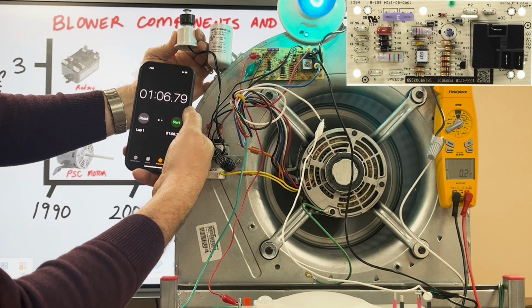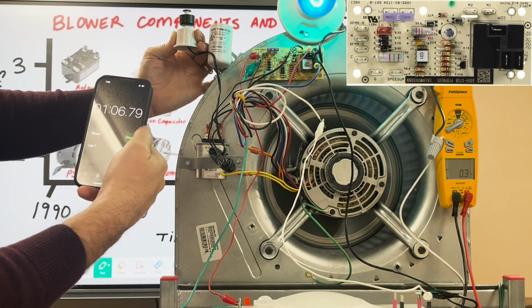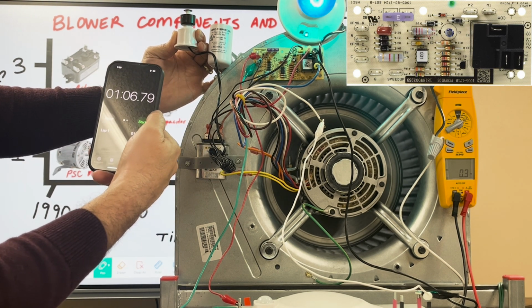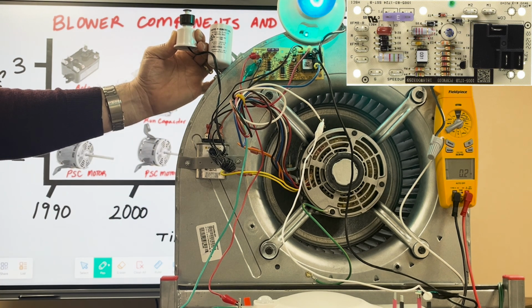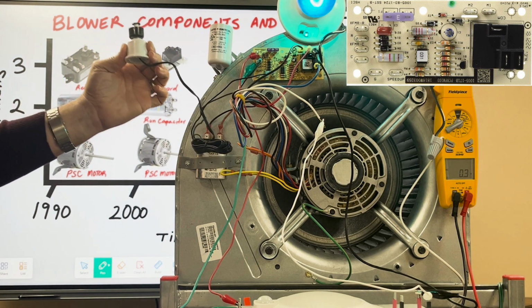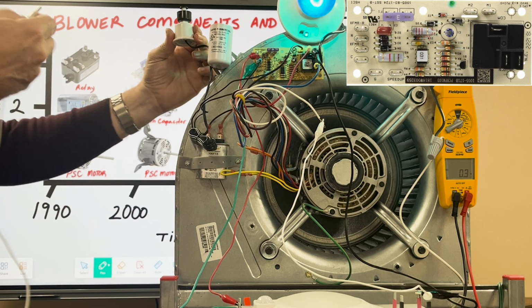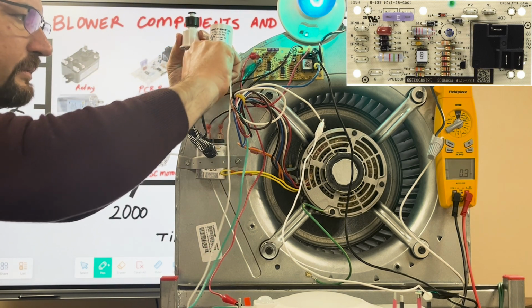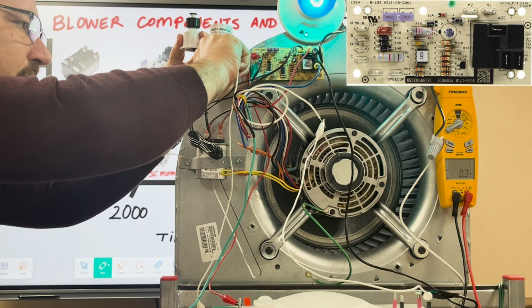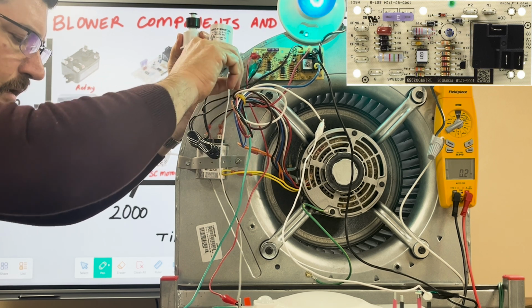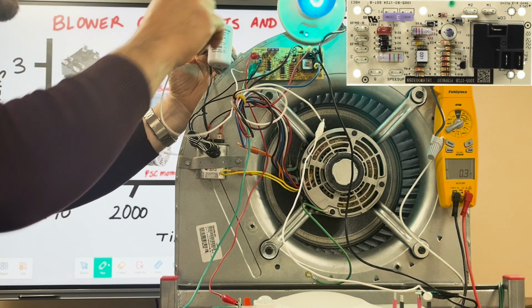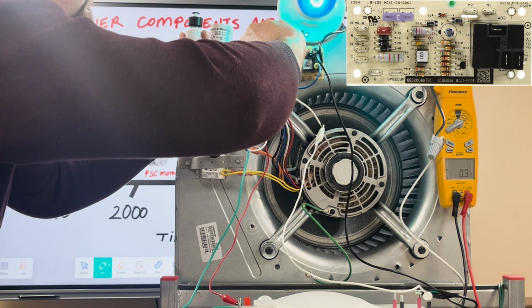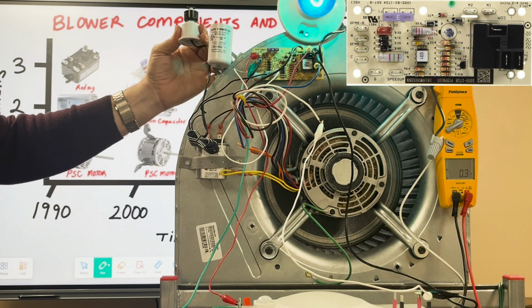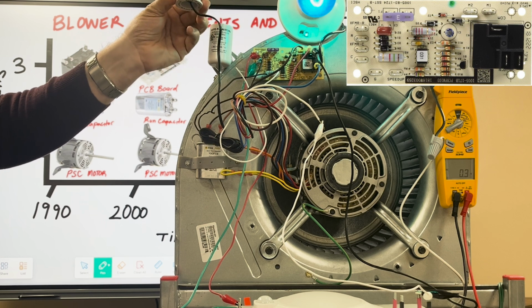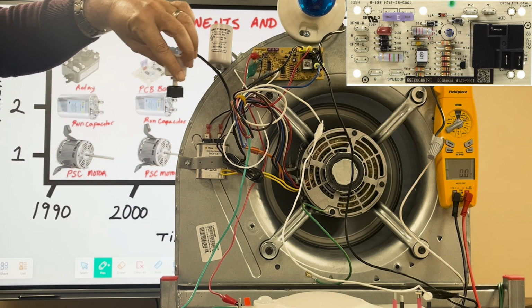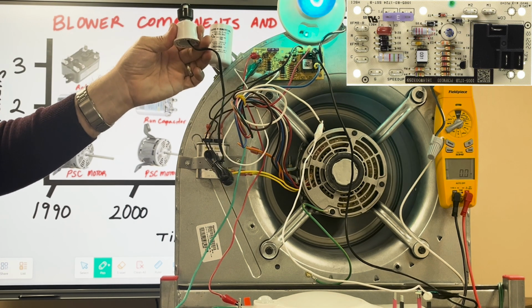And so that was about 65 seconds. And once again, if I were to short out between G and speed up, you'll notice that there is absolutely no time delay. So I'm going to go ahead and carefully get my alligator clip back there, and we're going to jump this out. There we go. So now that's shorted out. And once I give it a G call by flipping this over, it's instant. And once I lose my G call, it's instant.